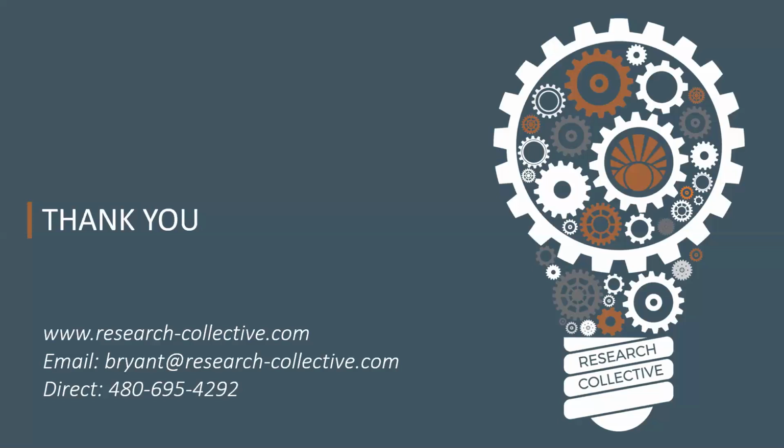But yeah, I've definitely seen that, and I think it's really worth it. One of the things that I would say in that case is a pre-sub is really helpful to get an idea of what all the testing is that's going to be required. Is a usability study going to be sufficient, or is another type of test going to be required as well?